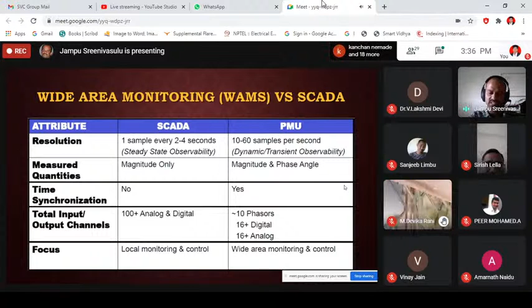Output channels are around 100 plus analog and digital with SCADA, whereas a phasor measurement unit has 10 phasors, 16 plus digital, and 16 analog channels. SCADA focuses on local monitoring and control, but a phasor measurement unit focuses on wide area monitoring and control. So a large area is monitored and controlled, whereas SCADA is restricted to local areas. These are the advantages of phasor measurement units with respect to the wide area monitoring system. These are the topics I wanted to discuss.